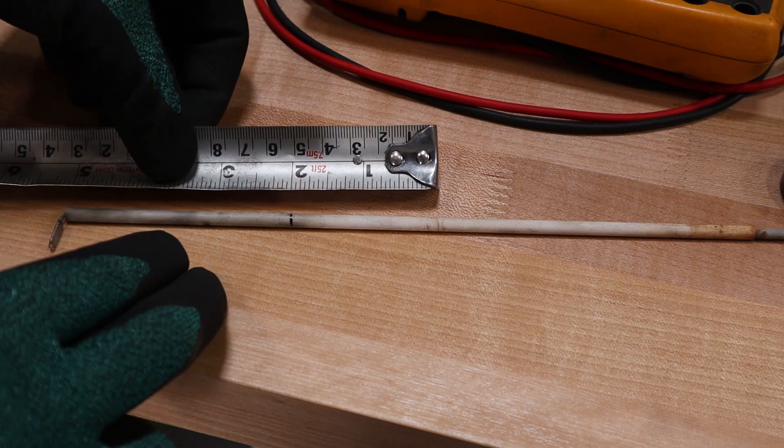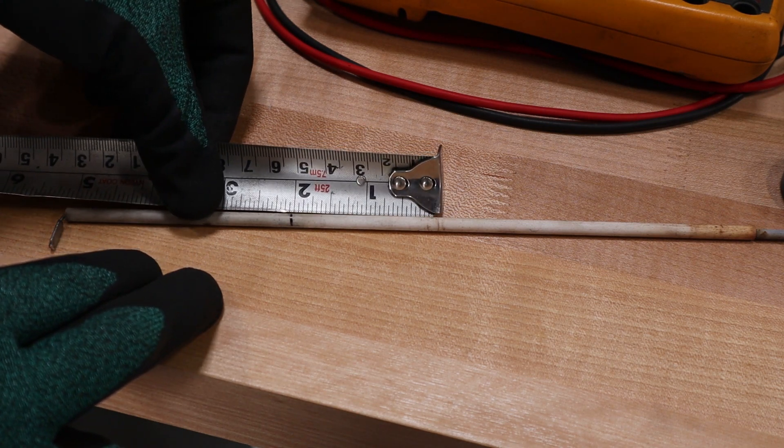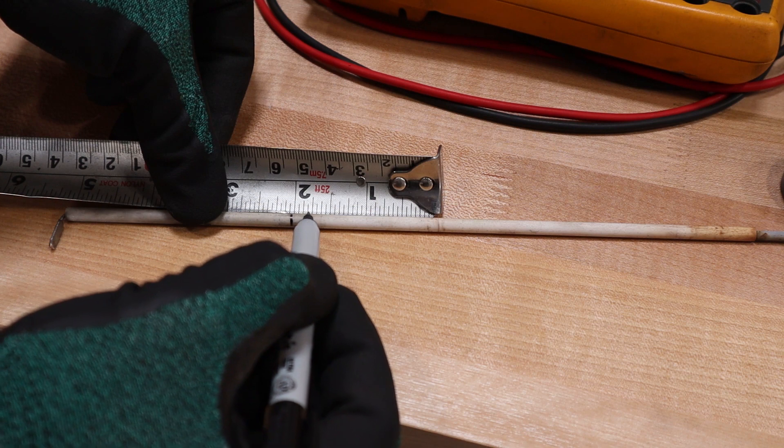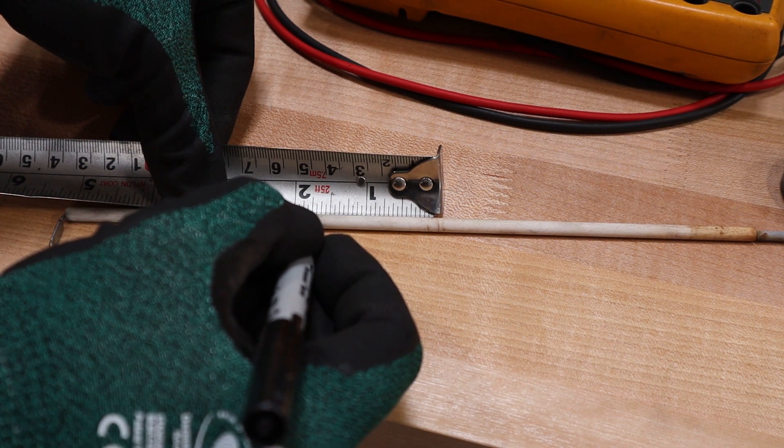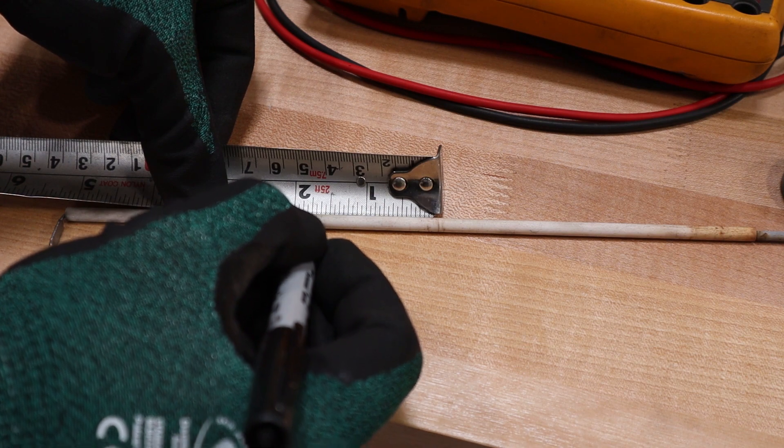All right, so now that we have the electrode out of the generator, we just want to take that mark and actually mark between an eighth and a quarter inch into the burner. So we're actually going to cut the difference and just do three sixteenths right like that.